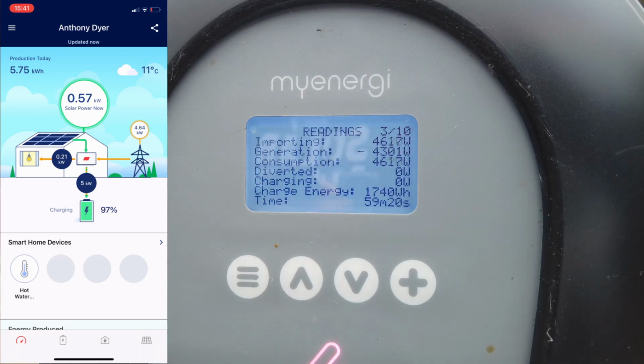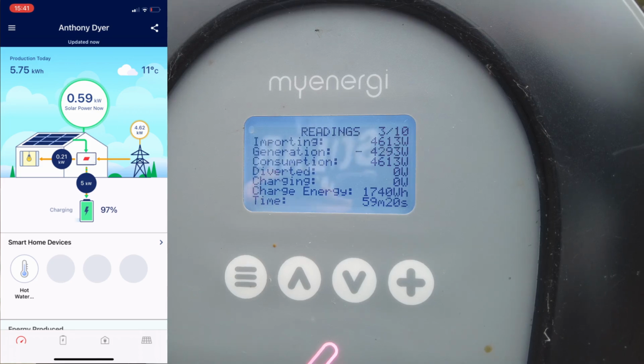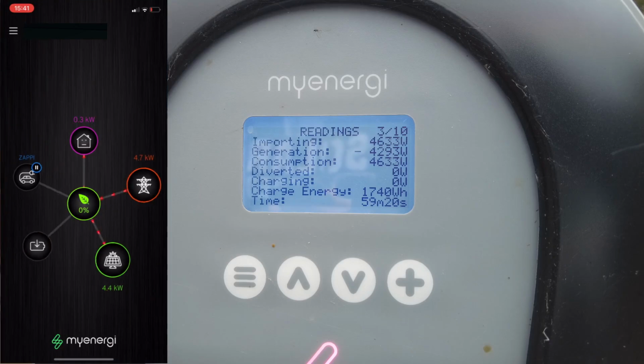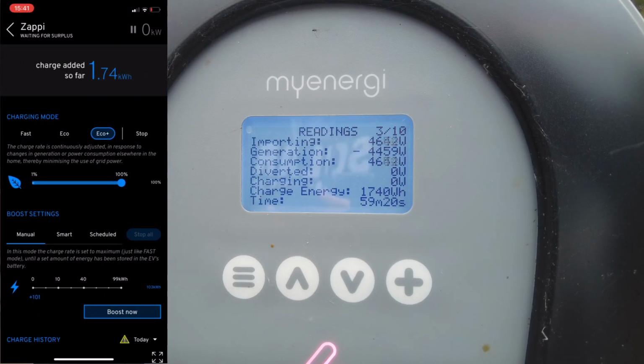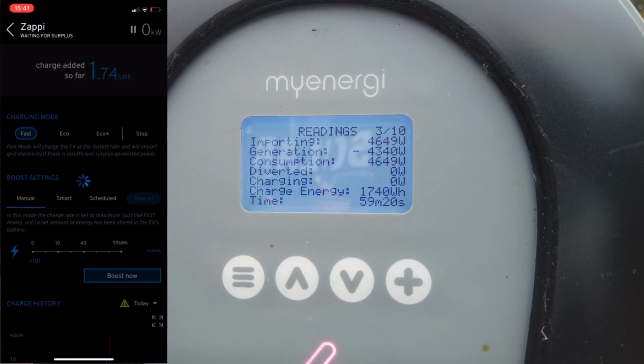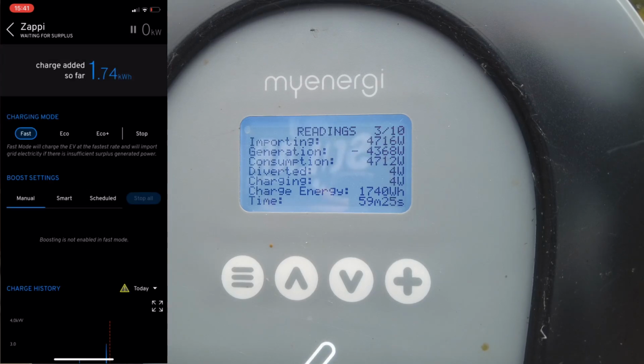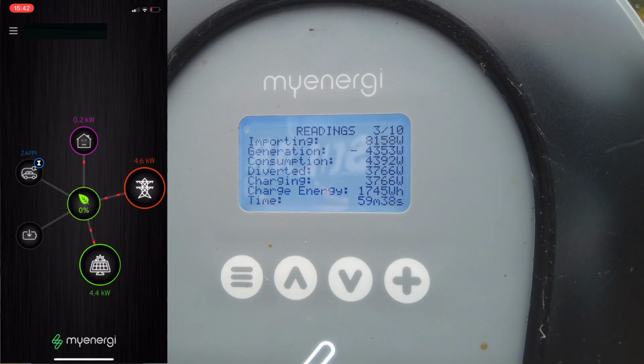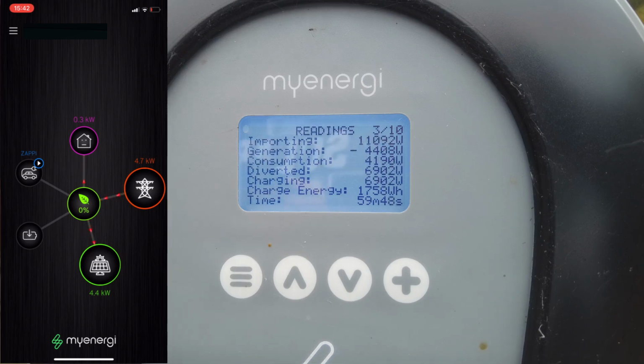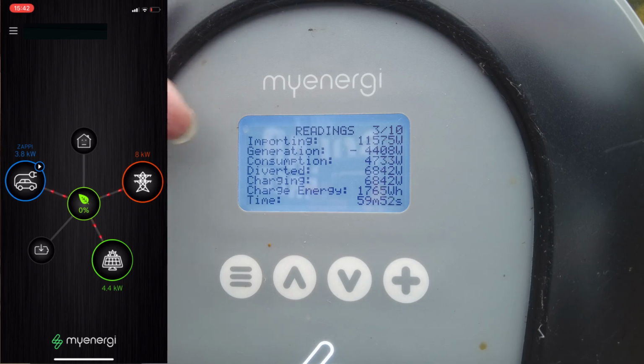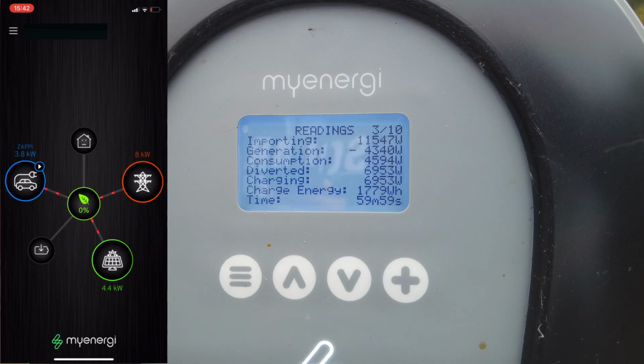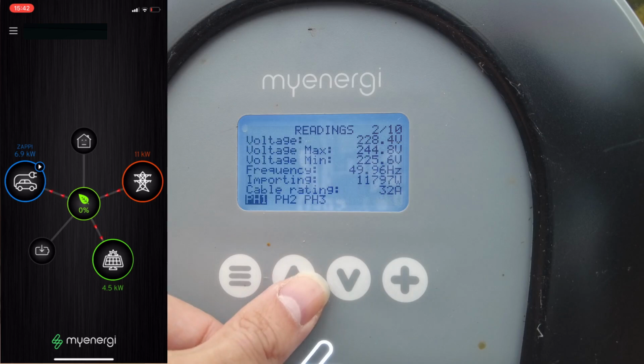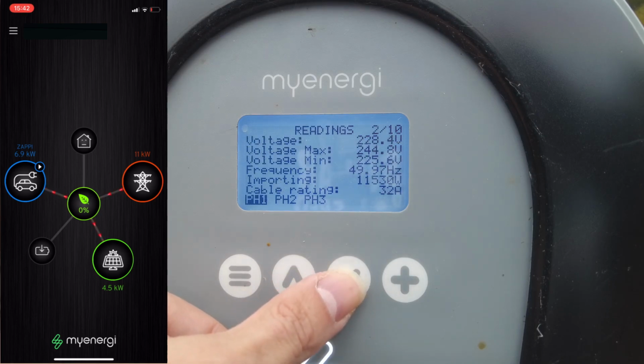What we're now going to do is add the car charging onto the load, and we're going to see whether 50 amps, which is about 12 kilowatts, whether it becomes limited to that. So now it's charging up. Okay, so now the import is ramping up. One of the things you can see is that the readings on the charger are updating much more frequently than the readings on the actual myenergi app. So we're getting close to about 11.5 kilowatts. That's very good. Let's just have a look at some other readings. So the voltage is 228 volts. We expect that. It's 11.5 kilowatts.